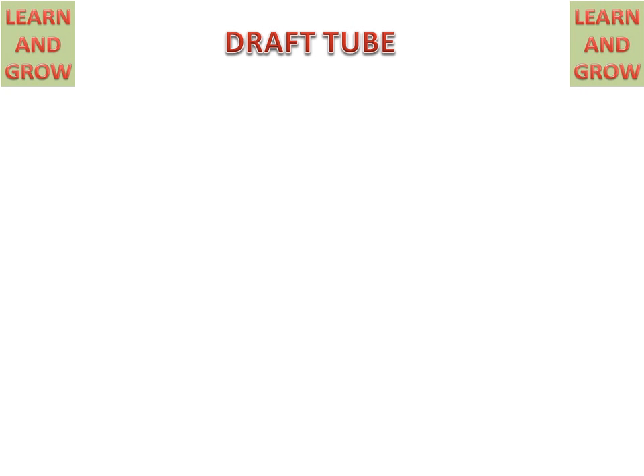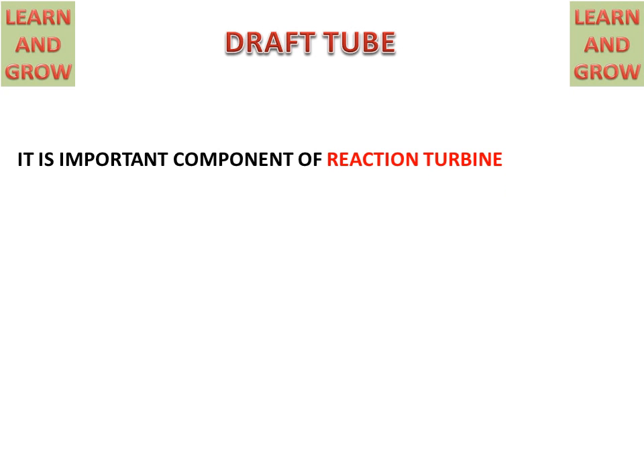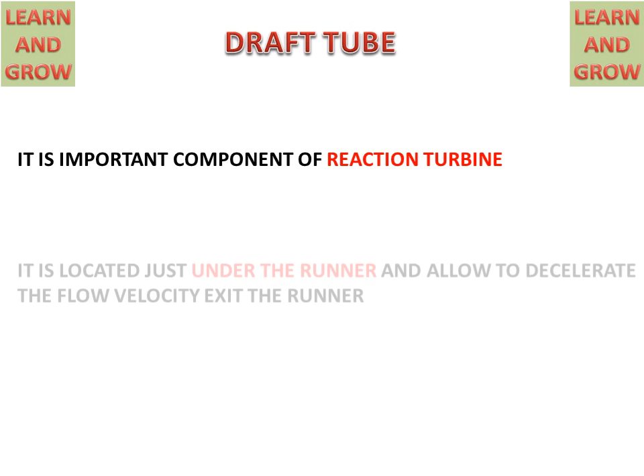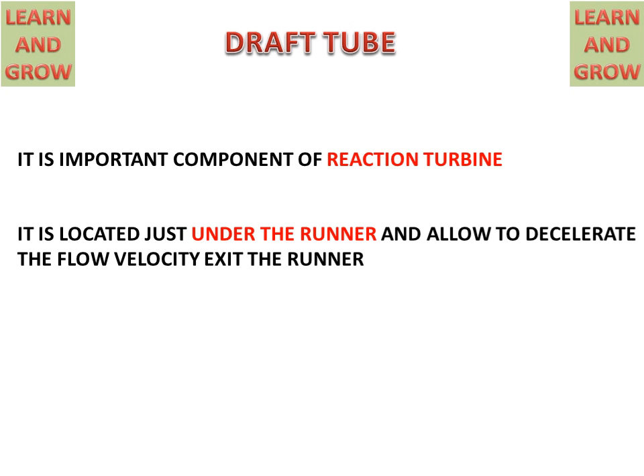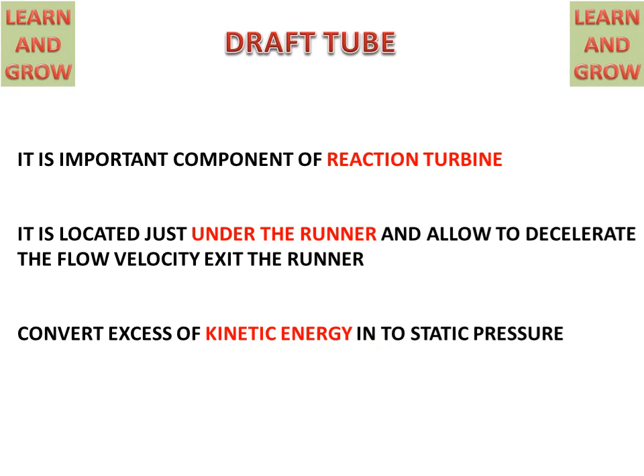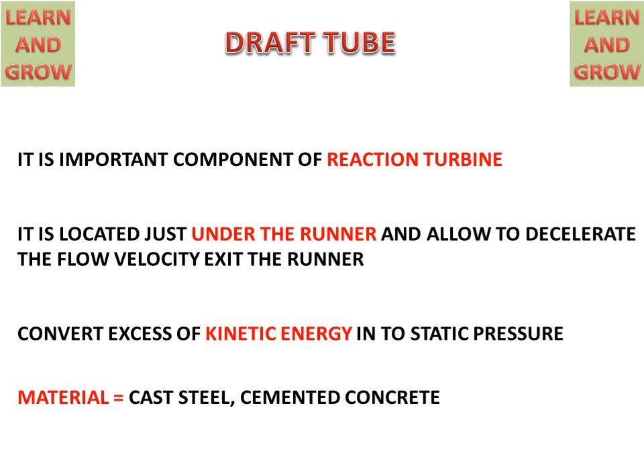Today we will discuss about draft tube and its types. A draft tube is an important component of a reaction turbine. It is located under the runner and allows the flow velocity exiting from the runner to decelerate. It converts excess kinetic energy into static pressure. The material used for the draft tube is cast steel or cemented concrete.